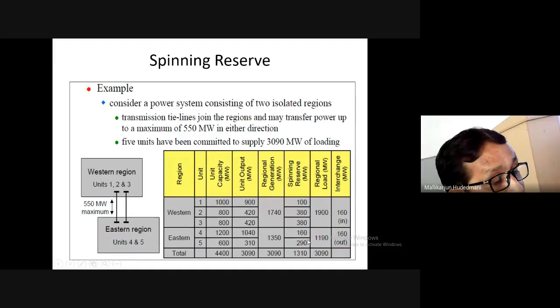See to this, 160 plus 290 megawatt. What is that extra available that can flow out of this to the neighbor corporation to make its requirement available? But there is an issue of pumping the power by the transmission tie capability, 550 megawatt only. Suppose there is a loss of a 600 megawatt generator which is developing 310. 310 is lost. Can I generate from this western area to pump power backward to the eastern to make up the loss? I can definitely do it because the capacity is 550.